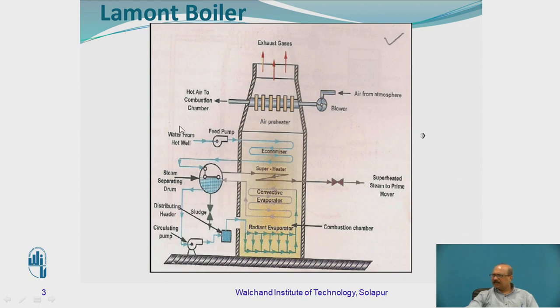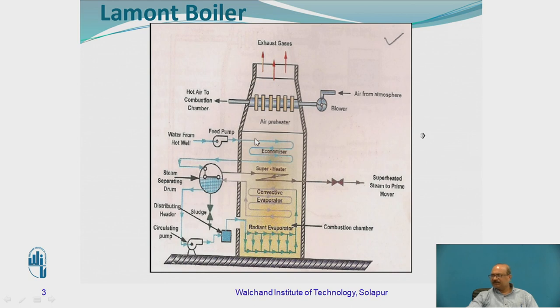Coming to this one — the water from the hot well is going to be taken through the feed pump. The important thing here: just observe, this is the feed pump — we are going to use it to pass the water inside the boiler through the economizer. This is below the air preheater. There is still a higher temperature available in this particular portion from the combustion chamber, so the available energy is going to be utilized for heating the feed water. We are going to utilize this energy to heat the inlet water, and then the hot water is sent to the drum.